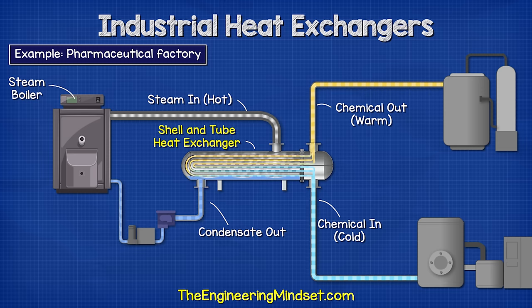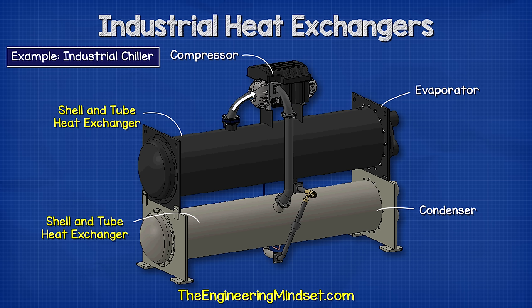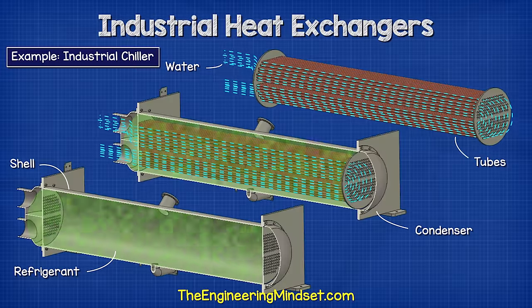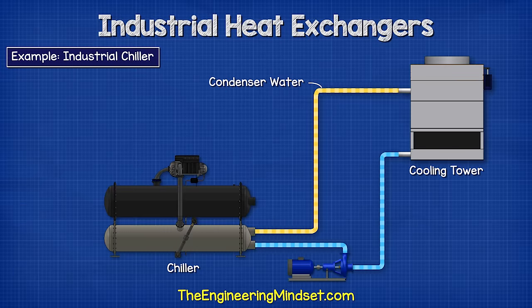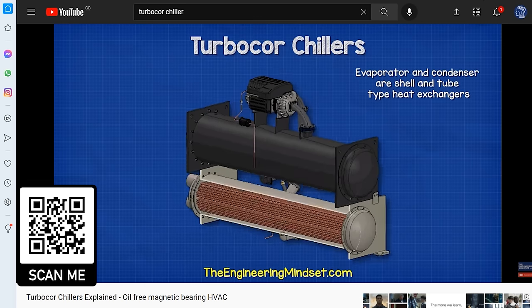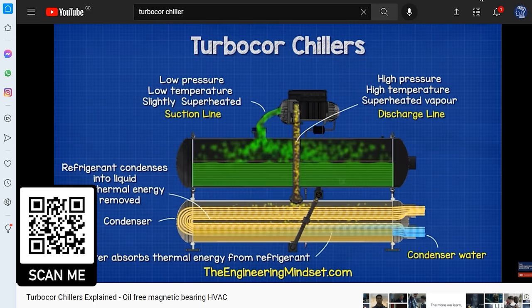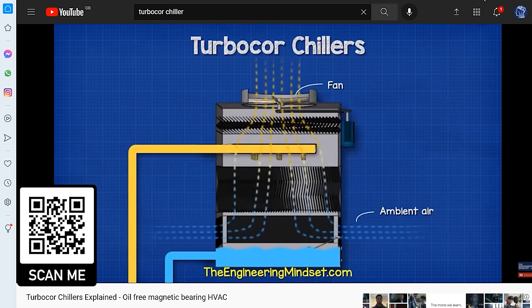Additionally, these are used in refrigeration applications like industrial chillers. We have water flowing through the tubes, with the hot refrigerant in the shell. The water absorbs the heat of the refrigerant so it can transport this to the cooling tower, where it is ejected into the atmosphere. The water returns cooler to pick up more unwanted thermal energy from the chiller. We have covered how chillers work in great detail previously — I'll leave a link in the video description below.